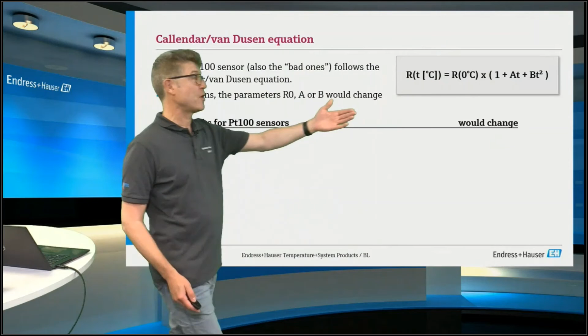We can change the basic resistance, the inclination, or, if there is a curve, the non-linearity, that's the word. So the main risk for a PT100 is the calibration itself. If you dump your naked measuring insert into your hot calibration bath, it's a thermal shock. The thermal shock is changing the basic value, and this is multiplied to the bracket, so the complete curve will be shifted to a different position. We will see it on the graph later on.